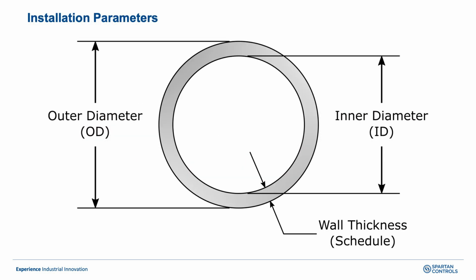Prior to programming the meter, it is best to confirm the following parameters for your application: outer diameter or circumference, wall thickness, pipe material, if there's any pipe lining, if there's any roughness of the pipe, the type of medium we are measuring, and the temperature of that same medium. For this video, we'll be working on a 2-inch Schedule 10 stainless steel pipe with water at 21 degrees Celsius.